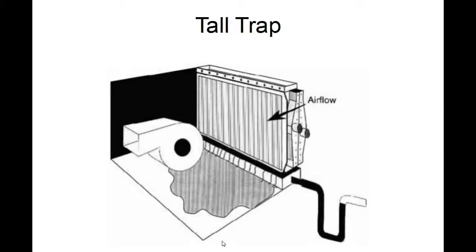Tall trap. If the trap is too deep or too tall, as illustrated here, there's not enough water pressure and weight of the water to force this column of water up through this trap that is too tall. Then what happens is it basically becomes a backed up system and the water instead of getting sucked and blown through the blower housing will overflow into the drain pan and into the air handler itself.